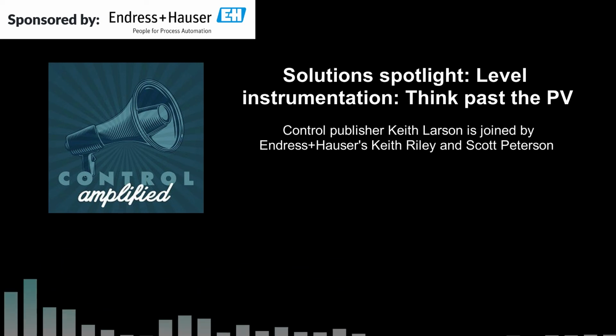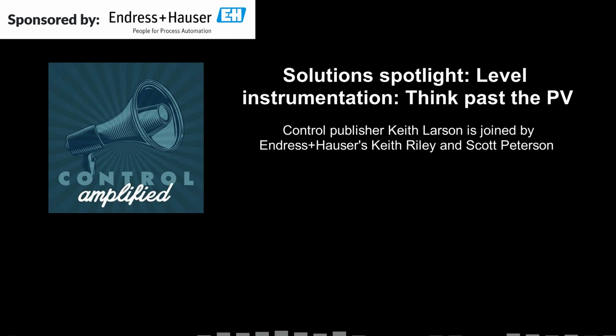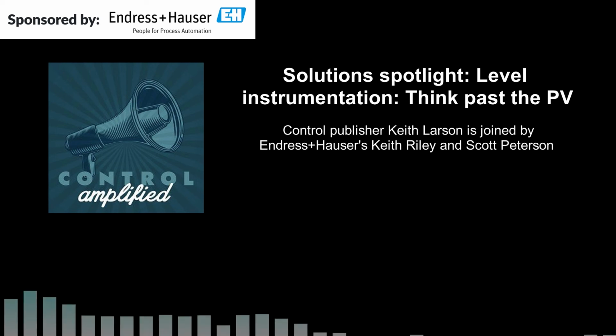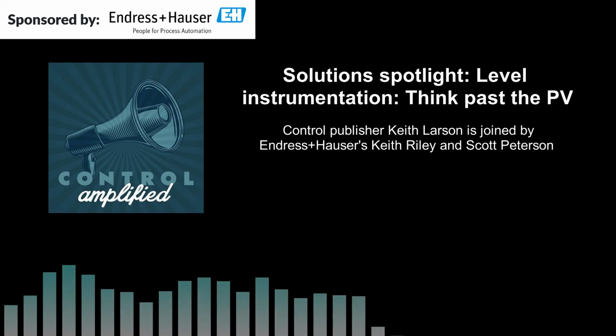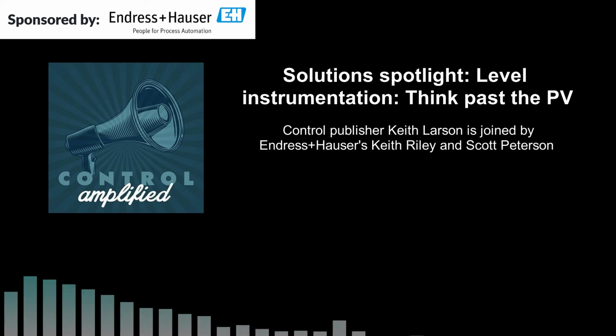Exactly. You just touched on the whole monitoring and the predictive maintenance at that particular point. Getting back to that whole idea that there's a whole lot of information that instrument is seeing that is not directly associated with the primary value or the measurement value. Signal strength. Perfect example of what you're talking about for foaming. Can you monitor the signal strength and set thresholds that once it starts to drop off can be an indication that you have foaming taking place? Most customers already know whether or not that process is prone to that kind of a situation. And by setting those thresholds, which the instrument then can alert you about, you can see, am I getting to the point where that's going to be a problem? And again, you can control your maintenance cycle that way.